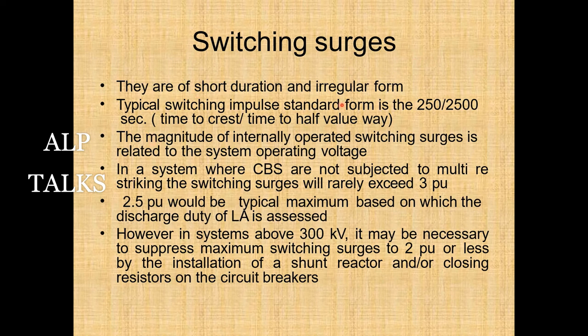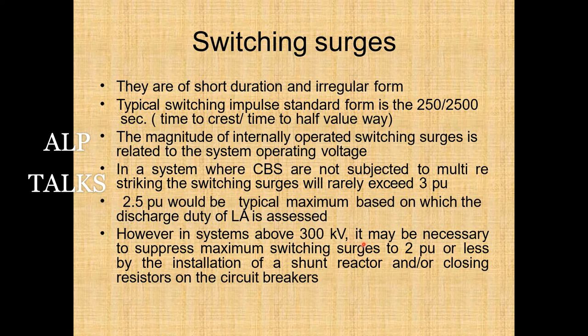Switching surges are short duration and of irregular form; the standard switching impulse form is 250/2500 microseconds (time to crest and time to half-value). Magnitudes of internally generated switching surges are related to system operating voltage. In systems where circuit breakers are not subjected to multiple restriking, switching surges rarely exceed 3 per unit — 2.5 per unit would be a typical maximum. In systems above 300 kV, it may be necessary to suppress maximum switching surges to 2 per unit or less by installing a shunt reactor or closing resistors on the circuit breaker.